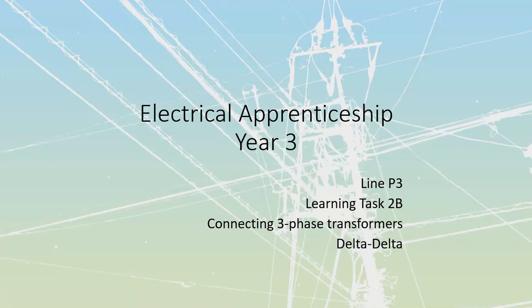The Y was a high voltage connection because we could get away with a high line-to-line voltage, but our phases only had to be insulated to the phase value. You could have a 25,000 volt line with only a 14.4 kV phase value to insulate to. But in our deltas, generally speaking, we're able to get larger line currents out with smaller windings, but we just cannot have any sort of unbalanced load with them. As soon as we unbalance the load, the windings would get differing values of voltage drop, and we'd start running into problems.